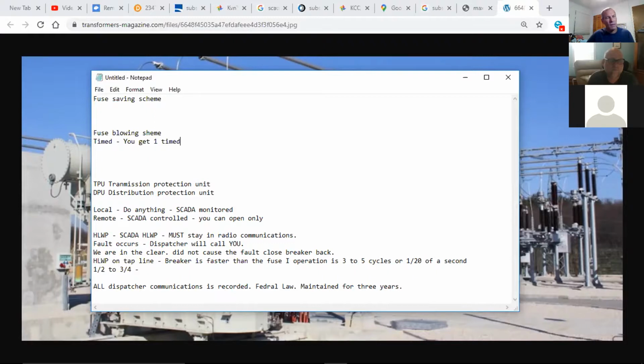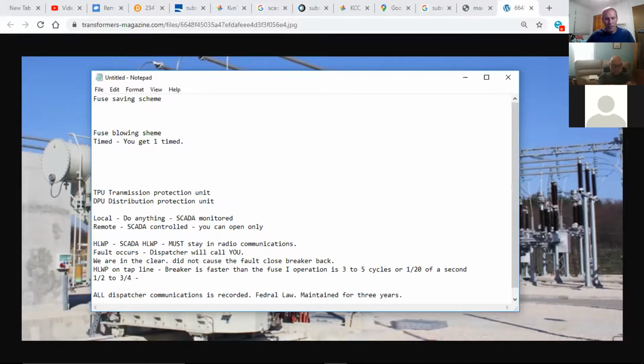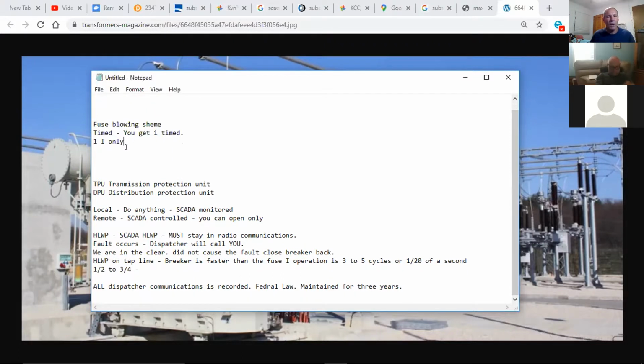That's not good. You get one-timed operation, and that's extremely bad. Instead of 3-timed, which it was set to, you get 1-timed. So I went back to our engineers and said you need to reconfigure so that when you go to a hotline work permit, I get instantaneous, one only. That actually took a good bit of work. Relays had to be changed out, configurations had to be changed, but that'll give you an idea of how those things work as far as instantaneous operations.